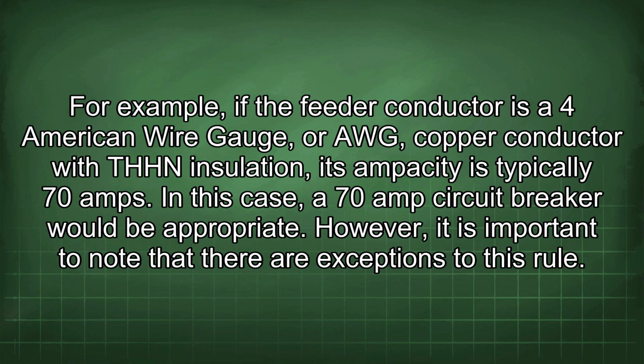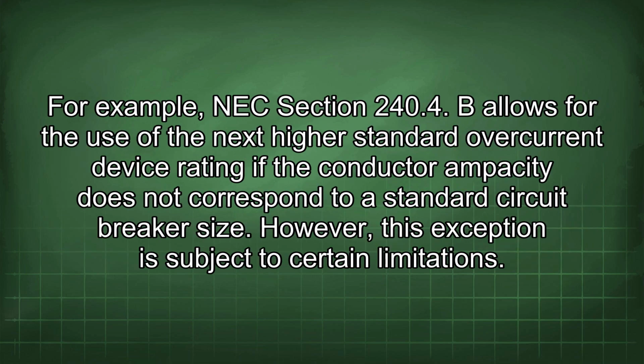However, it is important to note that there are exceptions to this rule. For example, NEC Section 240.4(B) allows for the use of the next highest standard overcurrent device rating if the conductor ampacity does not correspond to a standard circuit breaker size. However, this exception is subject to certain limitations.